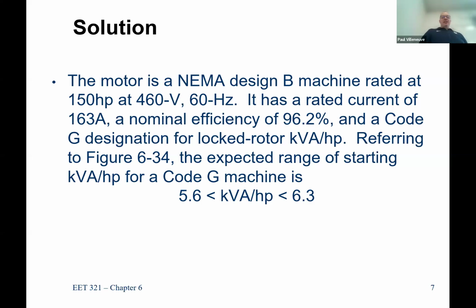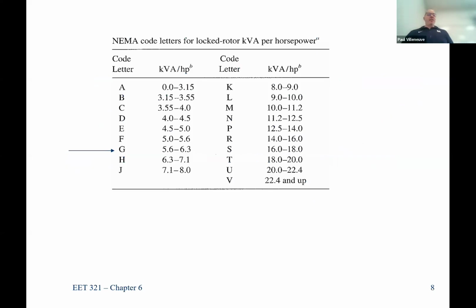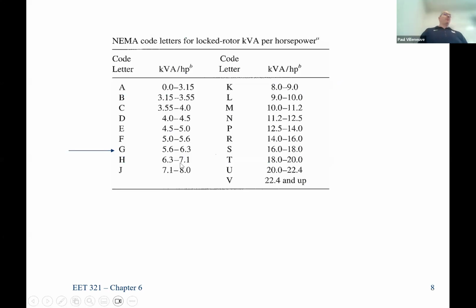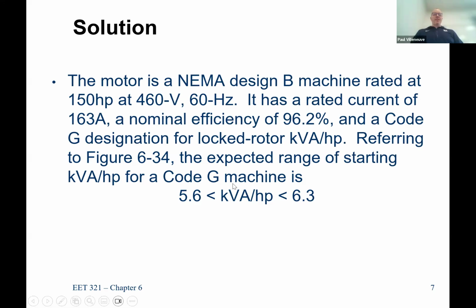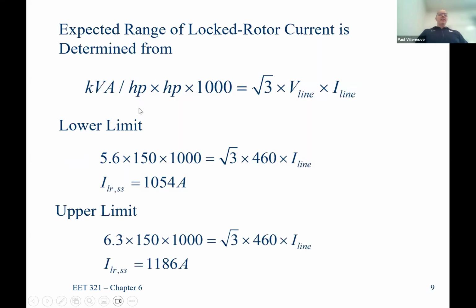It tells me I need so many kVA per horsepower to start this winding. Here's the figure that you need, okay? So in the example that we had here, that was a code H. So if we were doing that, it takes 6.3 to 7.1 kVA per horsepower to start that motor up. How do we use it? Well, for this one, it's code G. So we take our kVA per horsepower, whatever that range is. Then we multiply it by the number of horsepower. And then we multiply that by 1,000, right, to go from kVA to VA. And then we solve for I line.